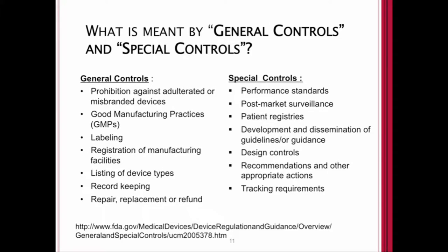What do we mean by general and special controls? General controls include prohibition against adulterated or misbranded devices, good manufacturing practices, provisions for labeling, registration of manufacturing facilities, listing device types, record-keeping controls, and repair, replacement, or refund in the event of recalls. Special controls deal with performance standards, including post-market surveillance, patient registries if needed, development and dissemination of guidelines or guidance, design controls and recommendations, and device tracking.